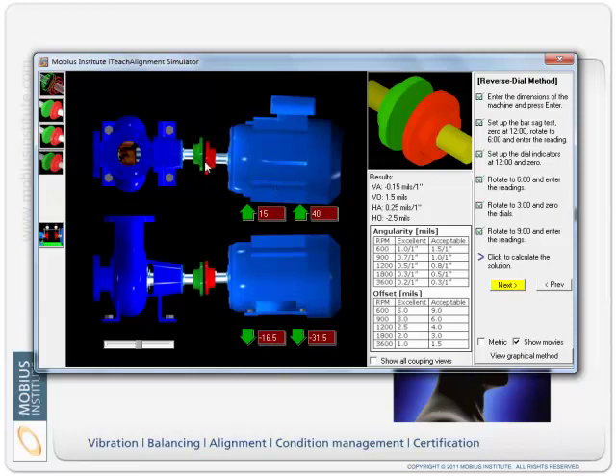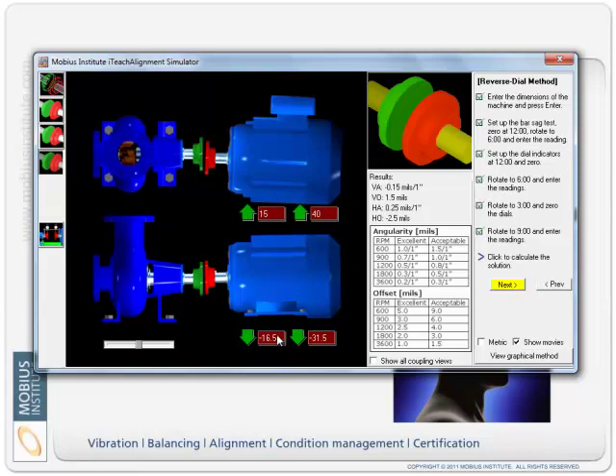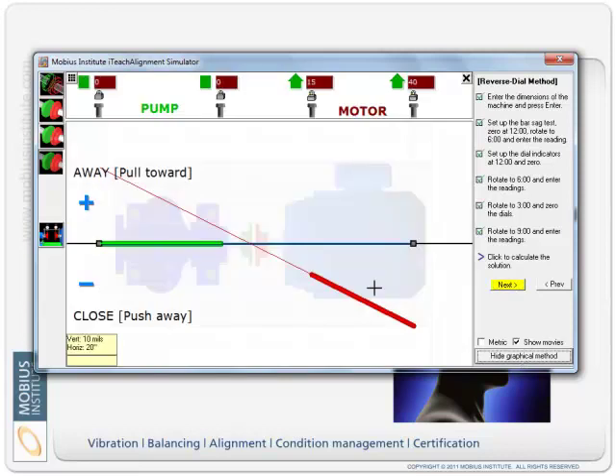So that's, we're looking down on the machine so we have to move it across that much. You can see that visually the motor is towards us so we have to push it away by this 15 and by the 40 here. You can see that it's up high so we need to drop it down 16.5 and 31.5.